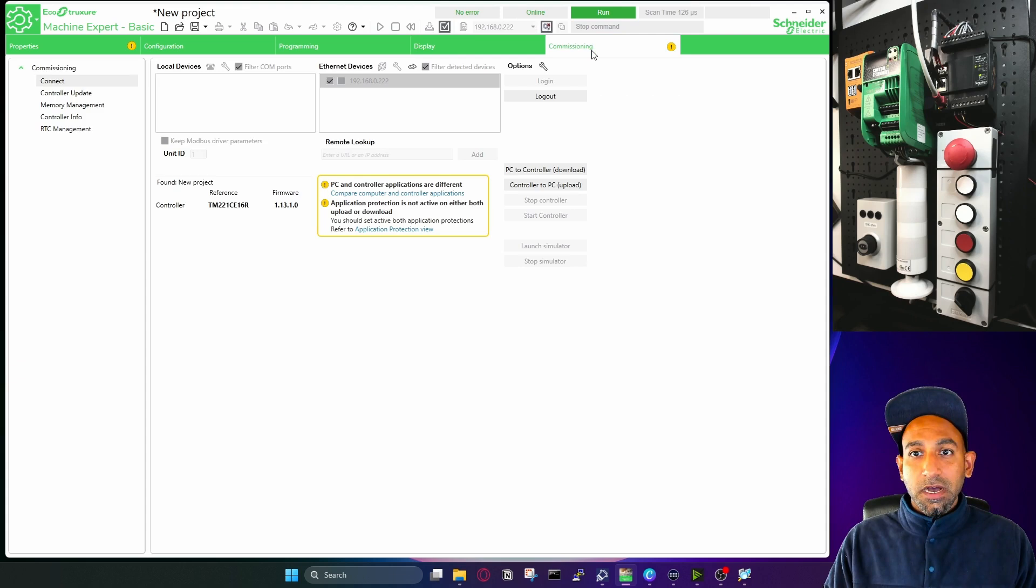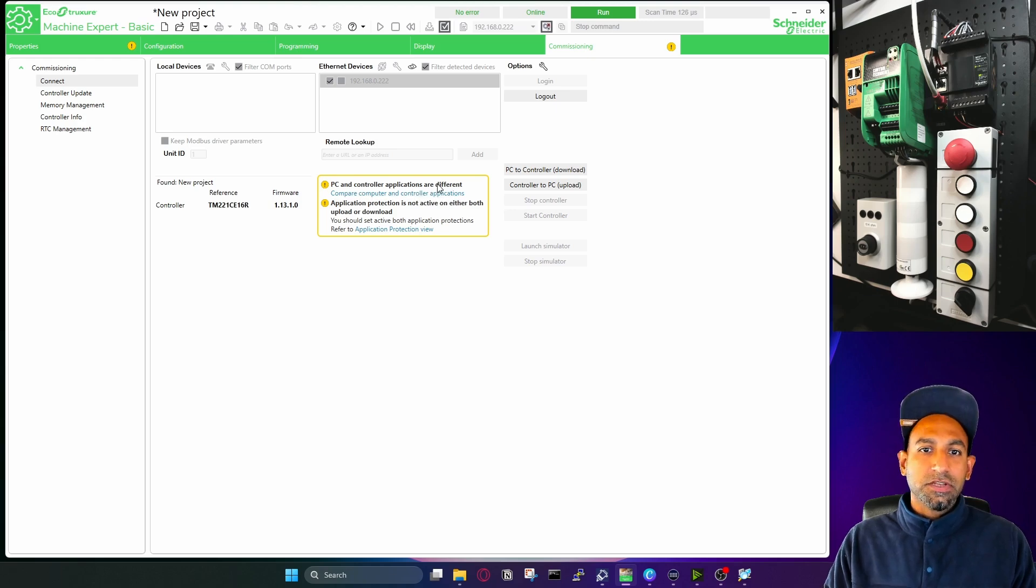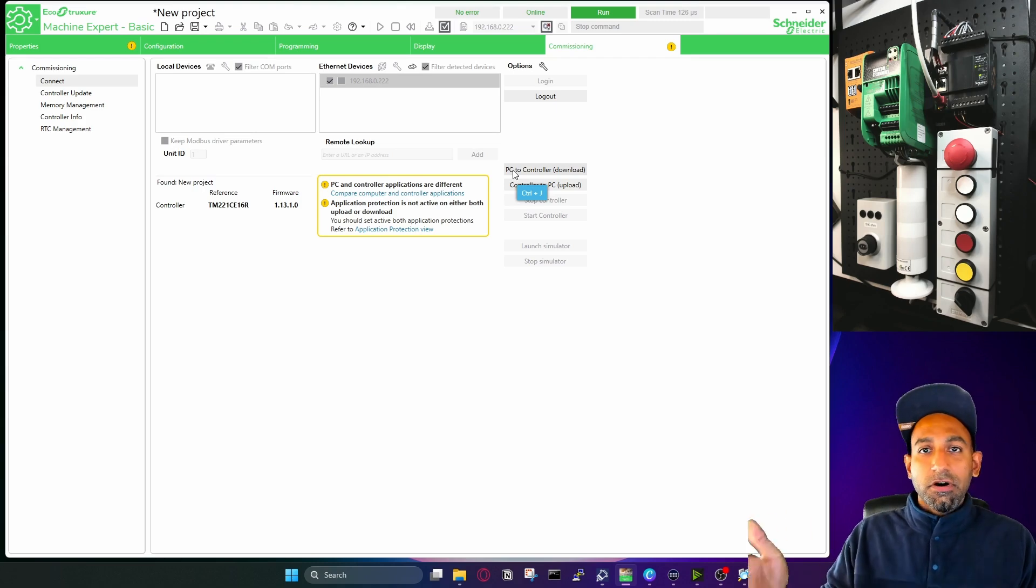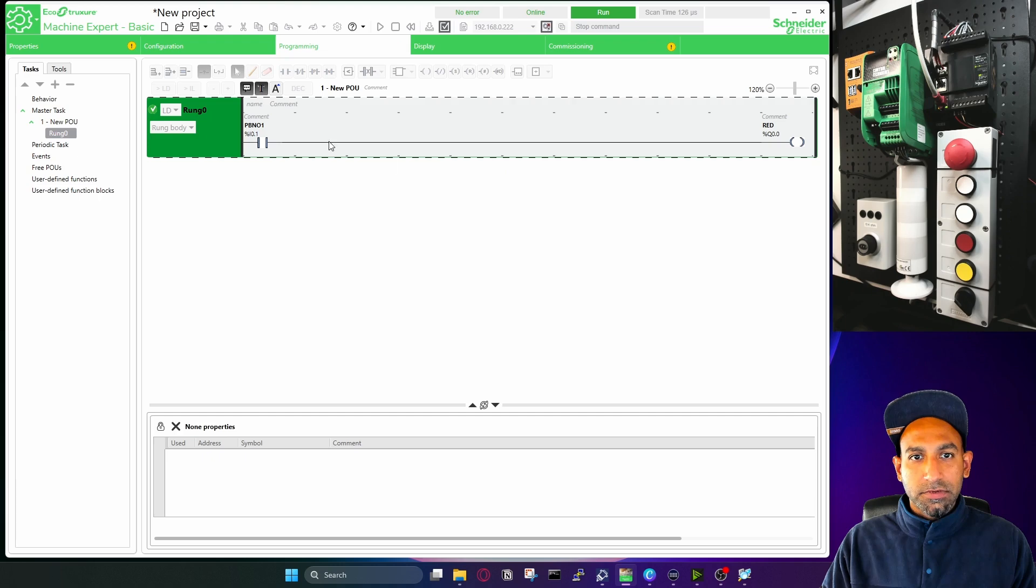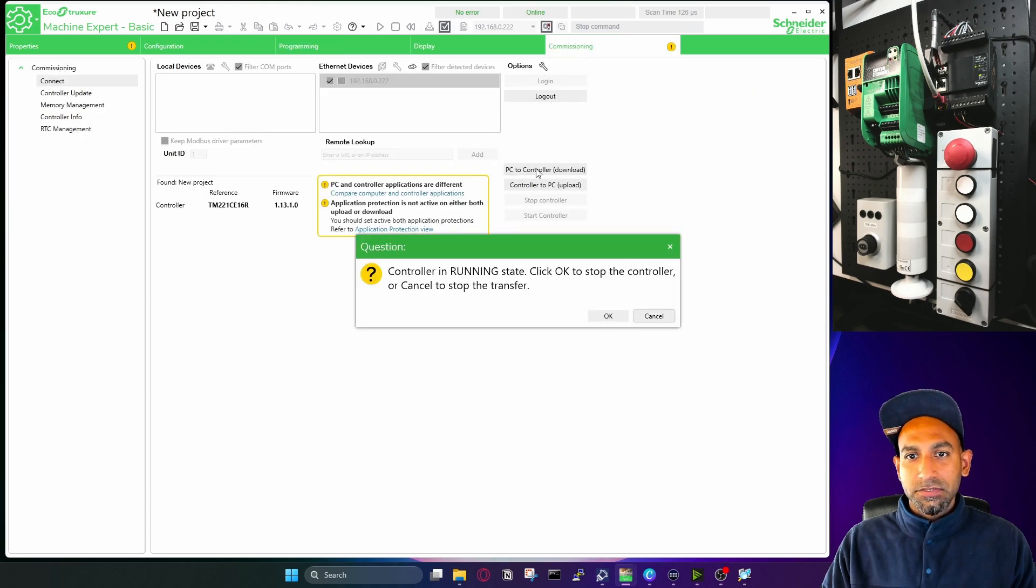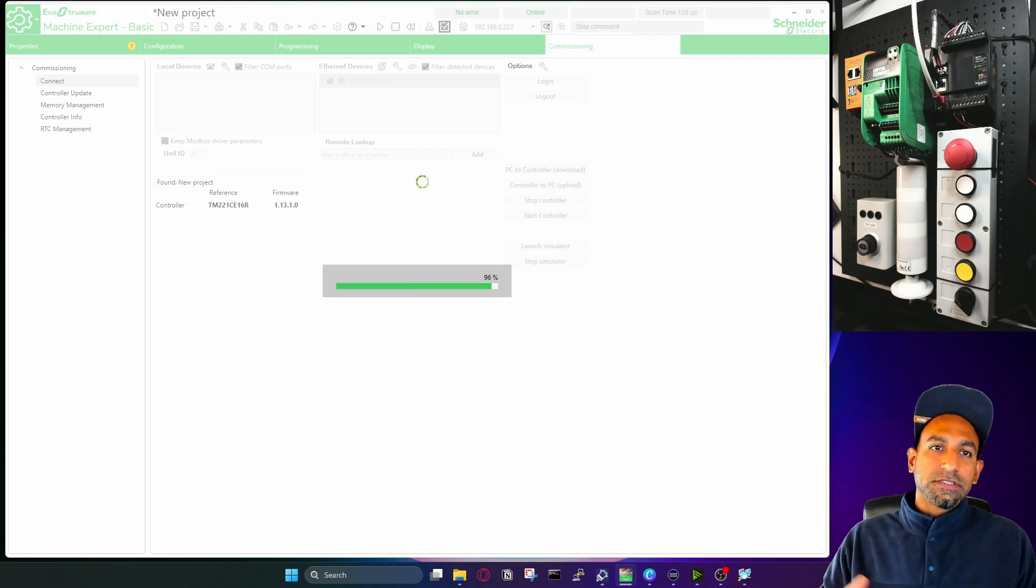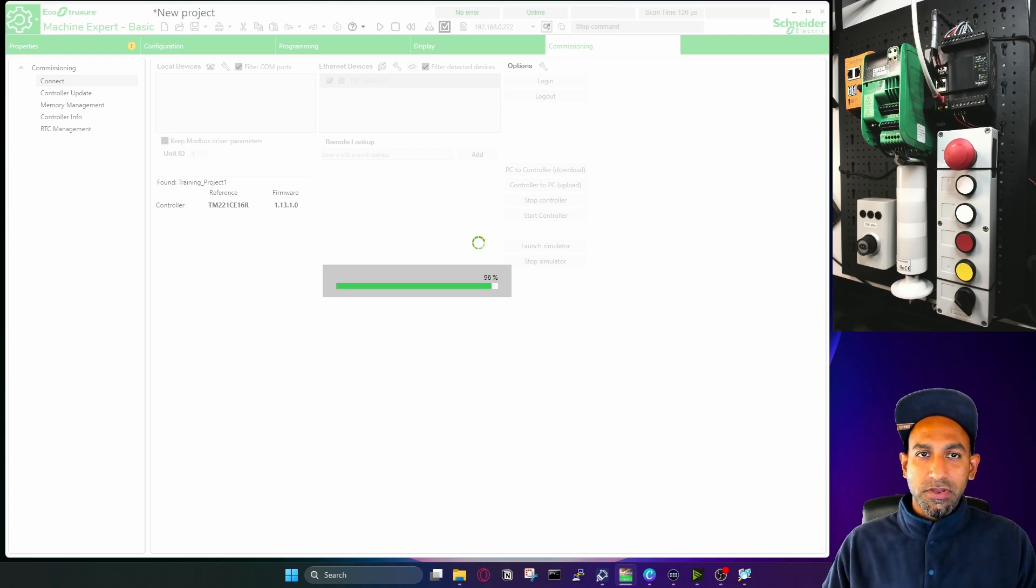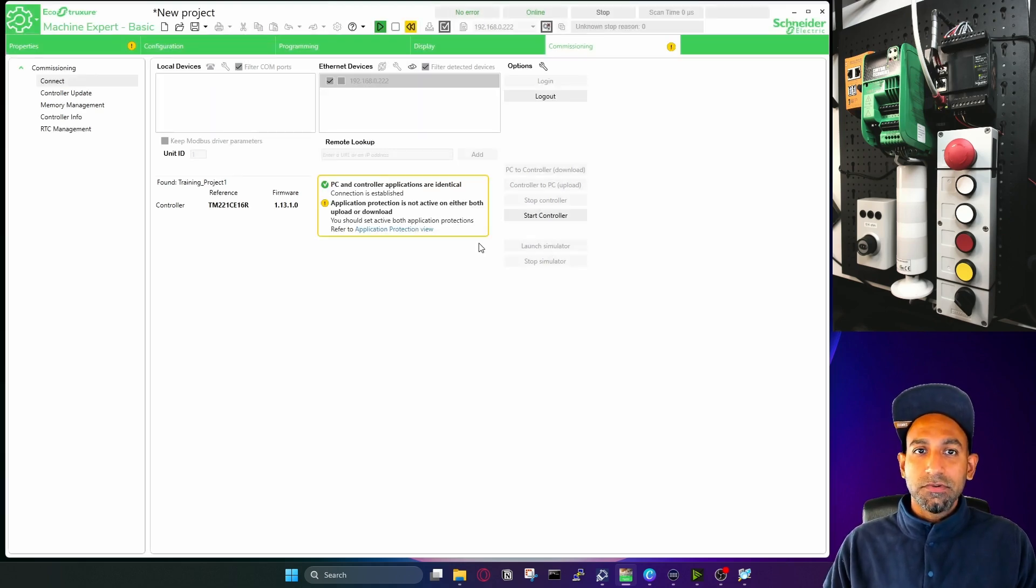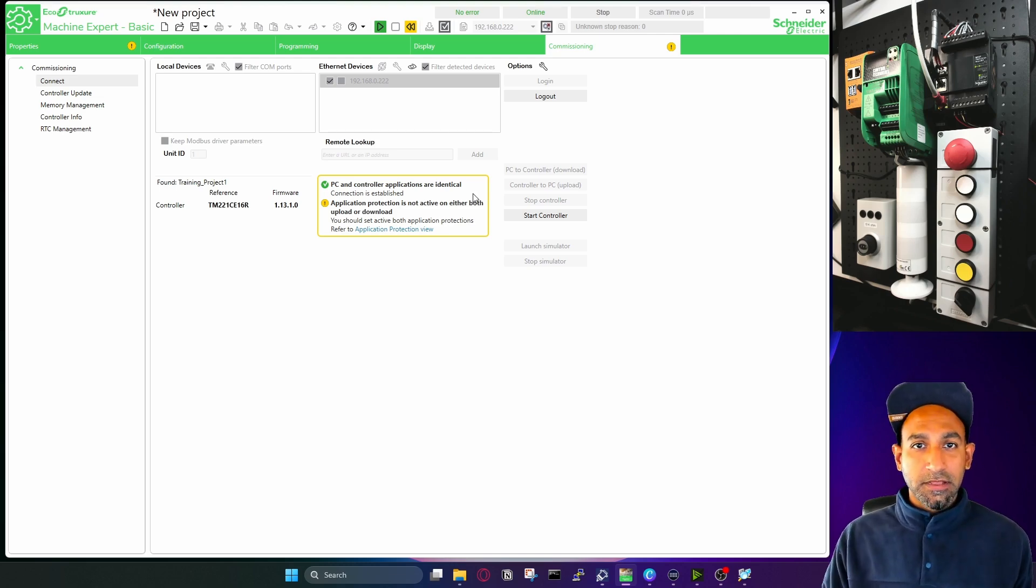Now we have to download the logic. In this case, it is also showing you compare computer and controller application, PC controller applications are different. So we will download either from PC to PLC or PLC to PC. In this case, I will do PC to controller because I want to download this logic. So click on PC to controller, click OK, click OK. And now it is downloading my program to the PLC. And once it's downloaded, the next step is you have to start the controller, you have to make it to run mode. So because every time when you download the program, it is in the stop mode by default. This is what the default settings are, although you can change that.